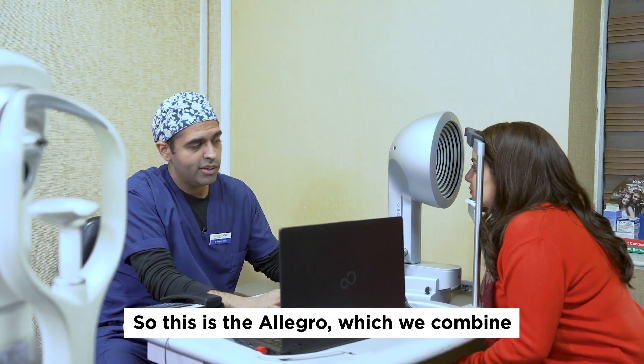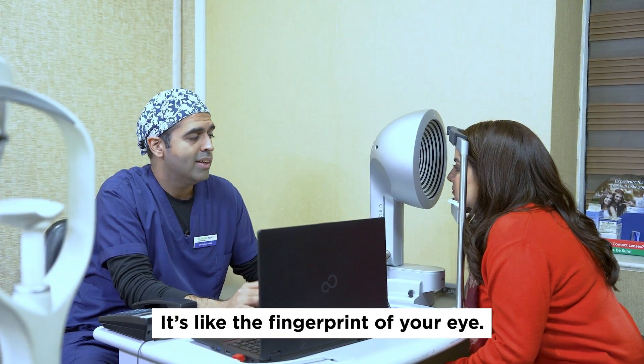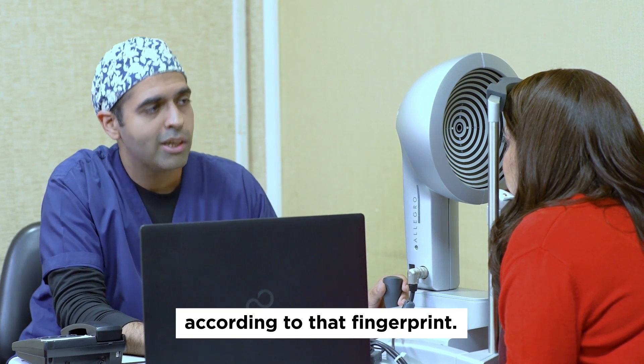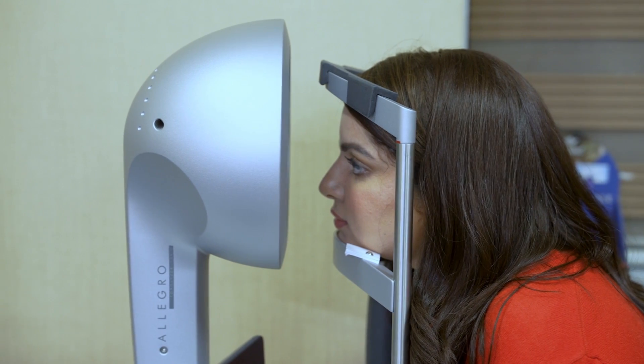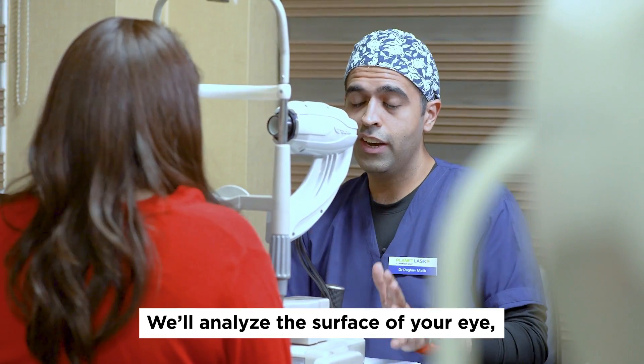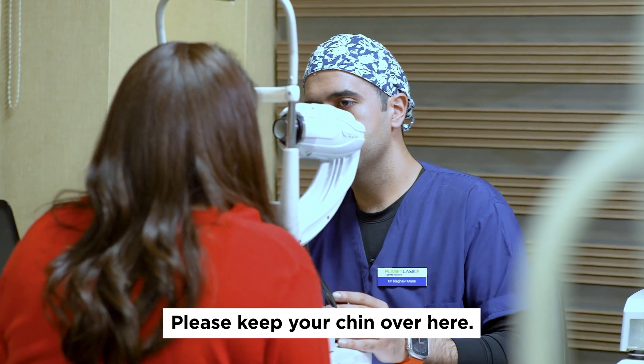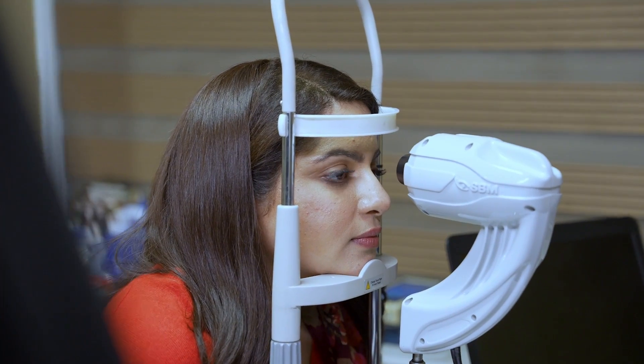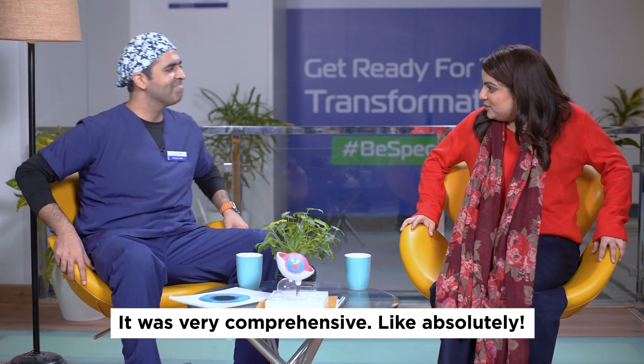This is the Allegro, which we combine or pair with our Contoura machine. This will map 22,000 points on your cornea — it's like the fingerprint of your eye. We capture that fingerprint and put it onto the laser machine, and the laser will fire according to that profile. Please keep your chin still. Look straight into the light. Blink. Sit back. Thank you.